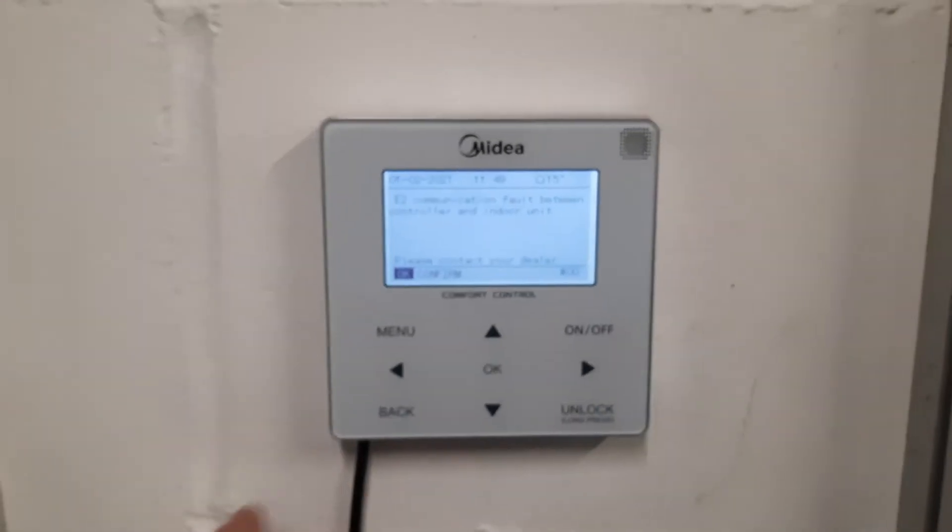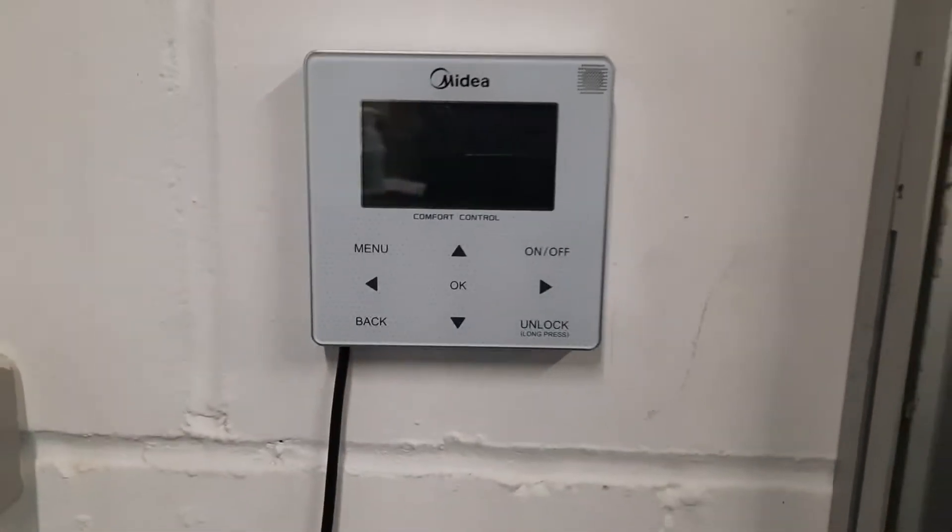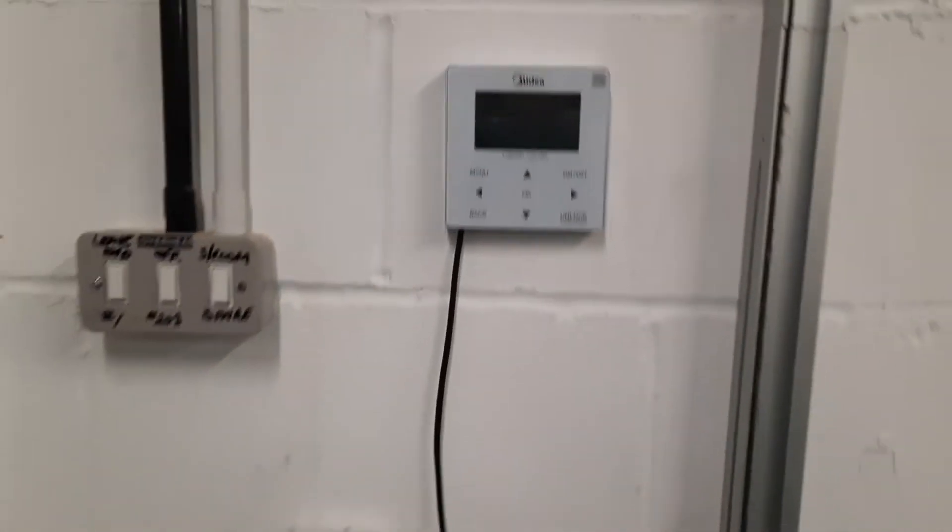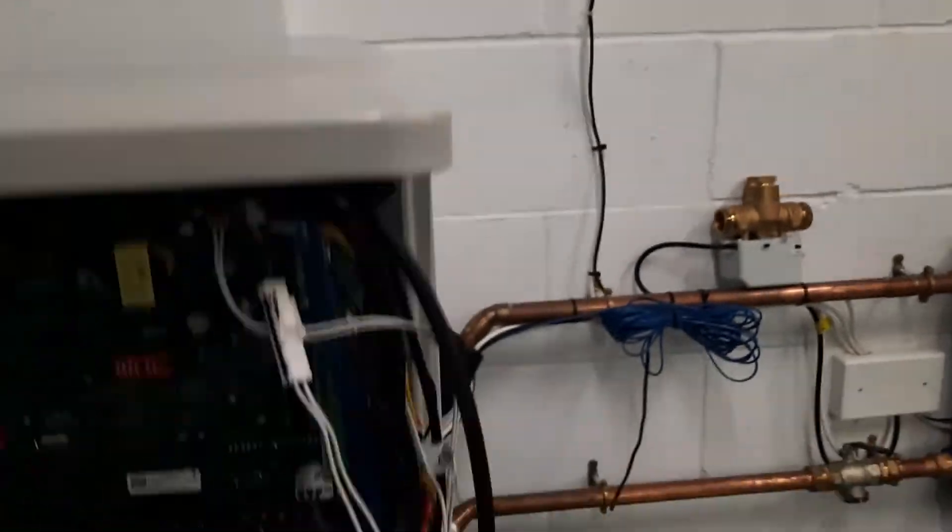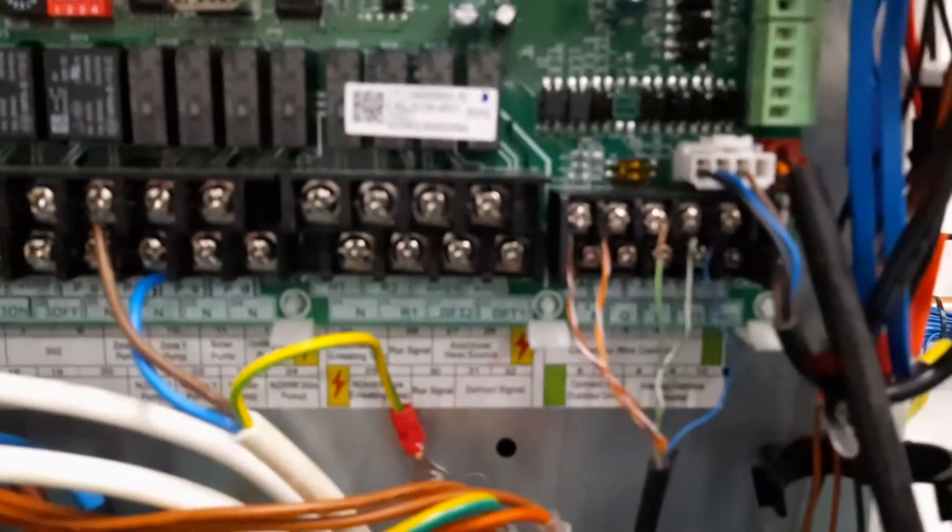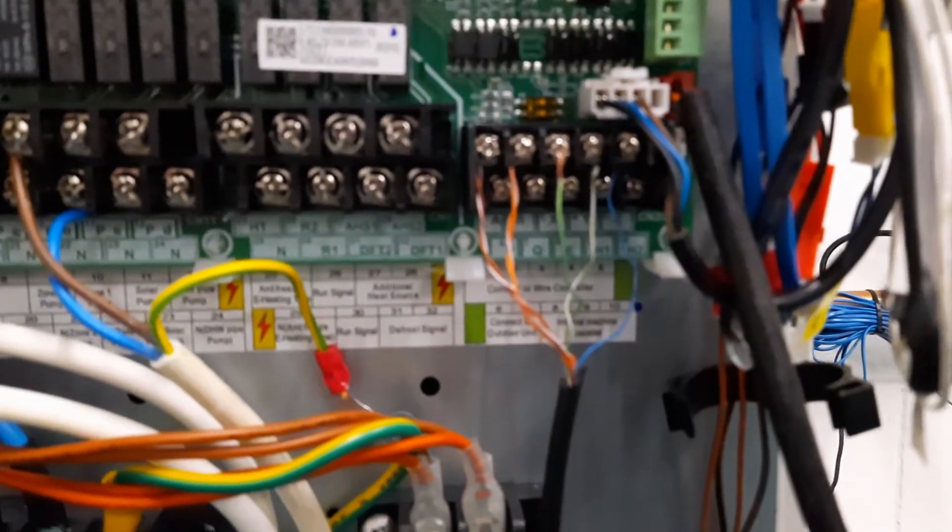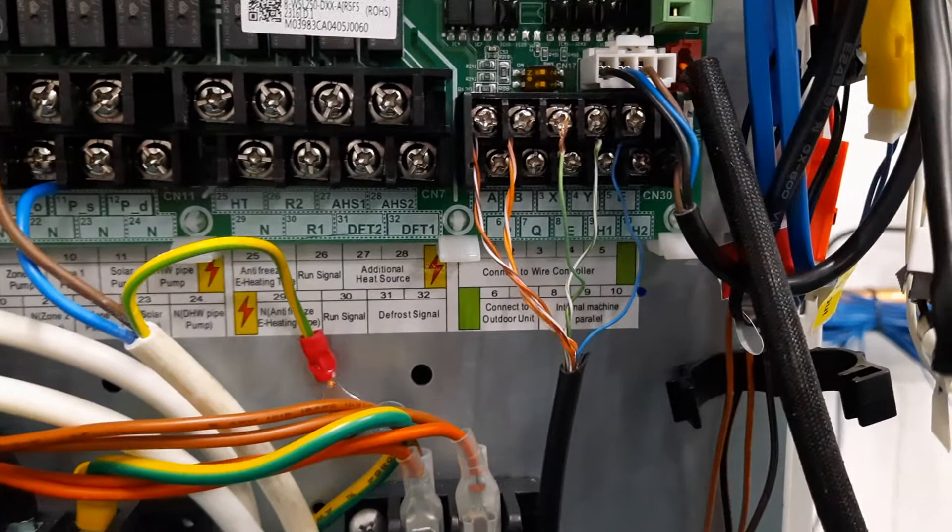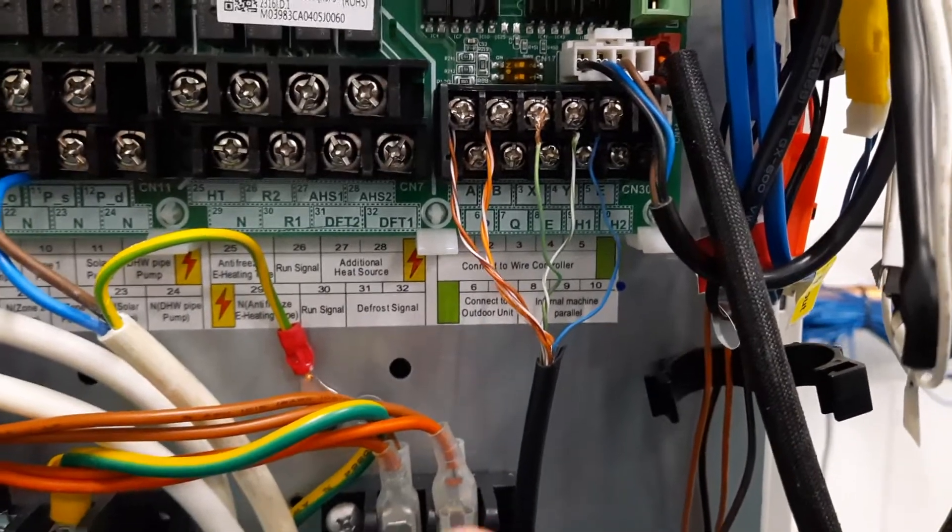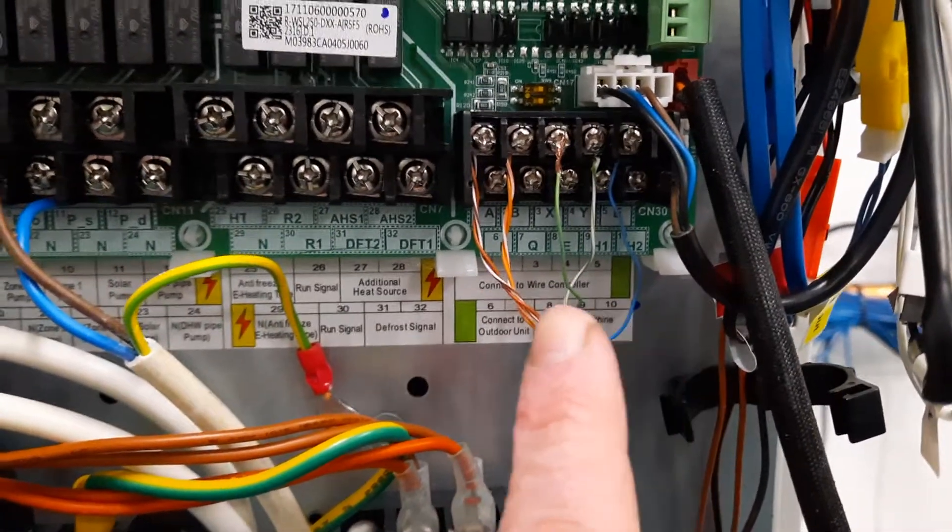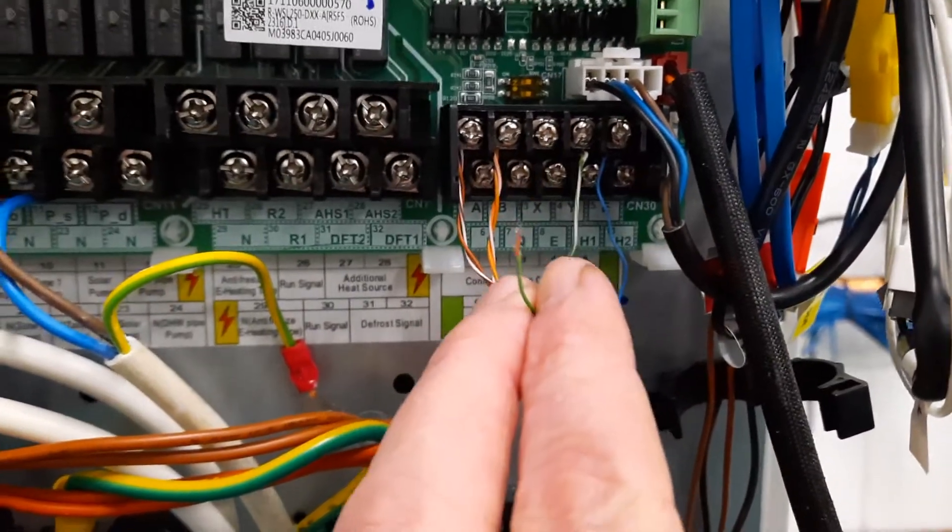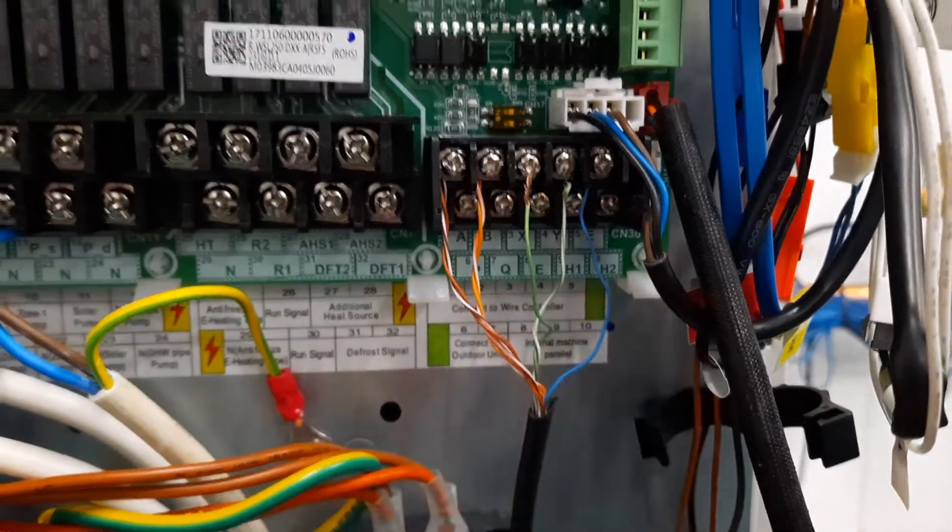Essentially what that means is that there's something wrong with this cable, which is a 5-core. This goes back to the outdoor unit and it connects in here on the bottom right hand corner of the PCB. You can see here that the 5 cores need connecting. This one here I've deliberately disconnected.